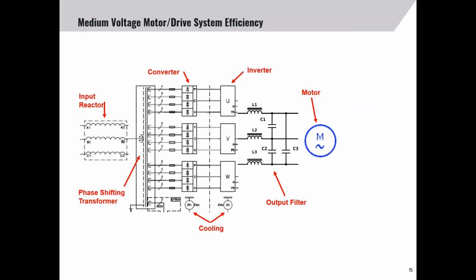So are there any efficiency standards for adjustable speed drives? Yeah, Mark, to my knowledge, there are no standards that mandate the efficiency of either low or medium voltage adjustable speed drives. Most low voltage drives have a similar topology with a diode front end, capacitors, and a transistor output. And the efficiency of those topologies is typically around 97%. This value is similar for medium voltage drives.